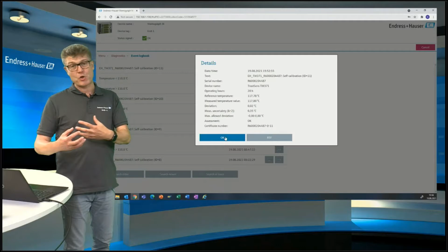This calibration is automatically performed every time the temperature drops in that way. And if you remember the application pictures, if you make milk and you shut off the milk heater because you want to clean it, you will pass the calibration point. If you do an autoclave sterilization and you shut off the autoclave, you will have a calibration. So every time, automatically, this calibration is performed during a cooling down process.